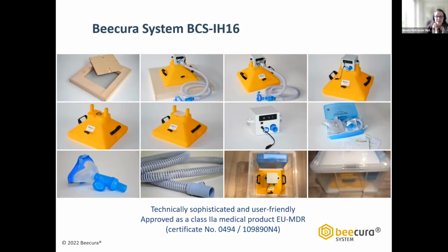That has a mask, a valve, and a heated hose. The valve has 2 openings. One makes sure that the person can't breathe back into the hose, so you don't have the risk of condensation or mold building. The air then flows out, and there's a lock so the room air can't enter the hose.